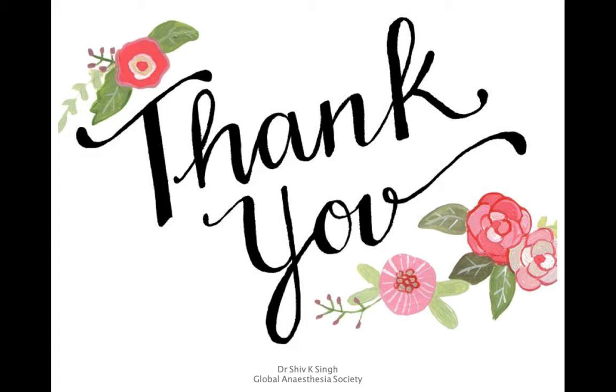So with this, we finish the lecture on the basics of vaporizers. To summarize, you need to know the principles of vaporization. As the liquid vaporizes, it drops its temperature. So in vaporizers, when the liquid anesthetic agents are vaporizing, they drop temperature, and this needs to be compensated. As the flow increases, if the output from the vaporizer is not increased, that will dilute the gases and drop the concentration. So you need mechanisms to maintain a constant concentration of the output.